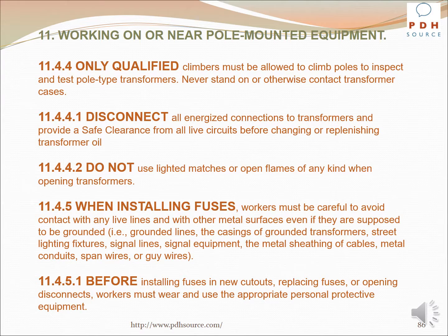Only qualified climbers must be allowed to climb poles to inspect and test pole-type transformers. Never stand on or otherwise contact transformer cases. Disconnect all energized connections to transformers and provide a safe clearance from all live circuits before changing or replenishing transformer oil. Do not use lighted matches or open flames of any kind when opening transformers.